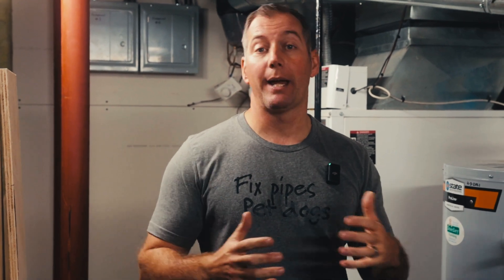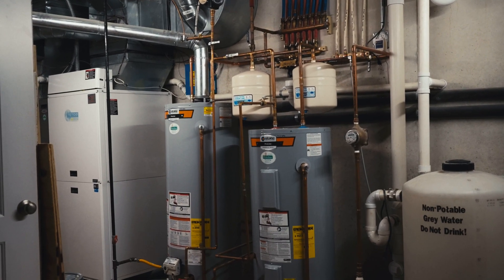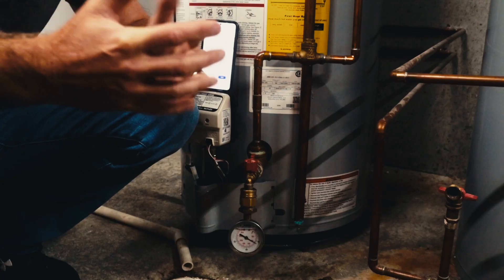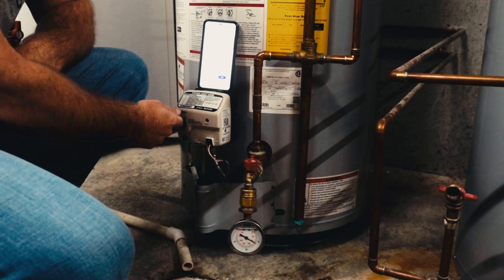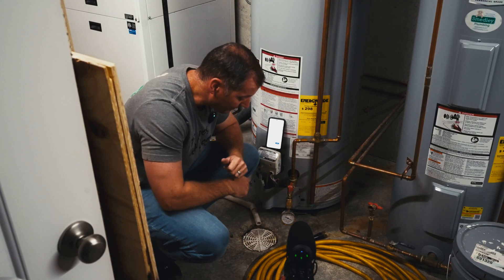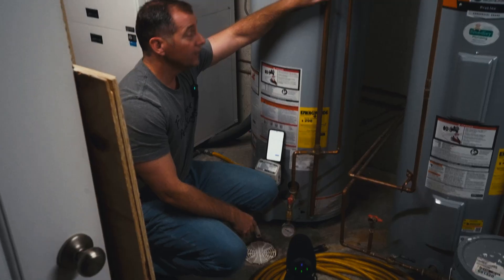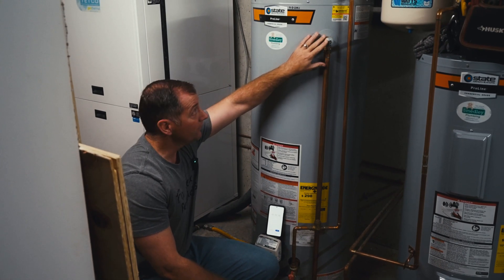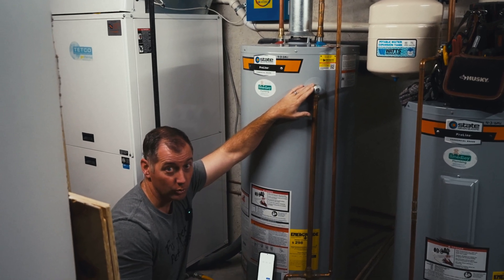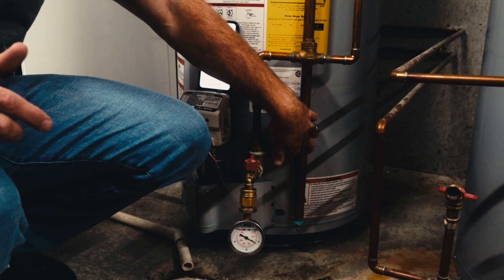Today's video is going to be about thermal expansion. We've got a gauge on the bottom of the tank, and right now the gauge is reading about 60 pounds of pressure — the same as my house pressure. We're going to turn this on, start our stopwatch, and measure how much time it takes for the gauge to climb. As it gets upwards around 100 to 150 pounds, it's going to force the relief valve on the water heater to open. This valve opens at 150 PSI or 210 degrees, or a combination of the two. As we warm up and get close to 150 pounds, we'll see water dribbling out of the bottom of the relief tube.